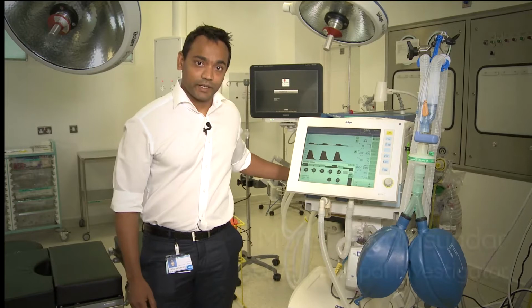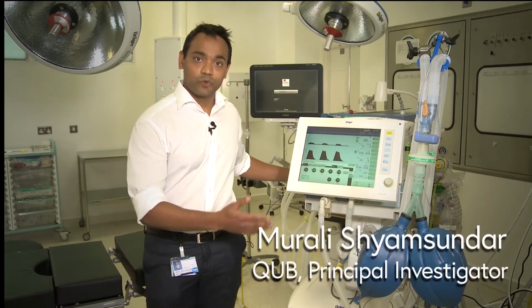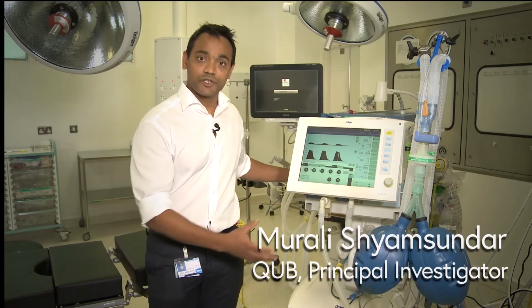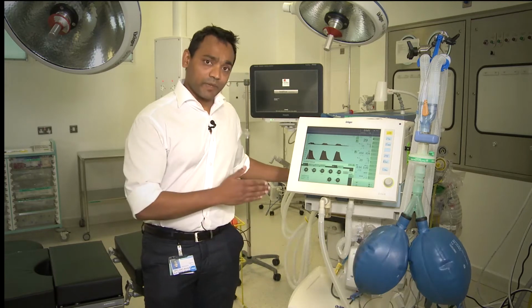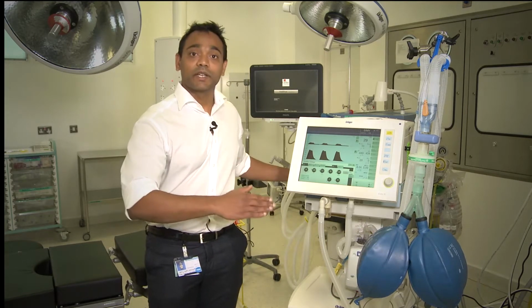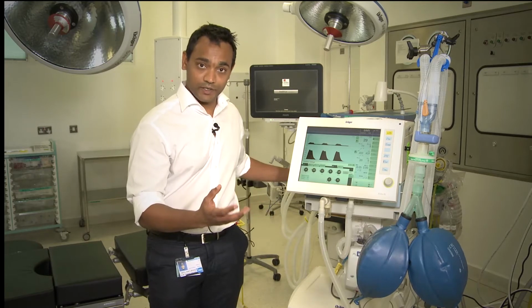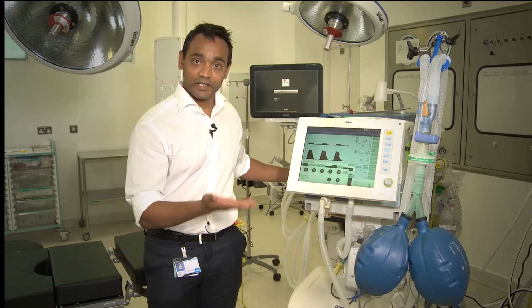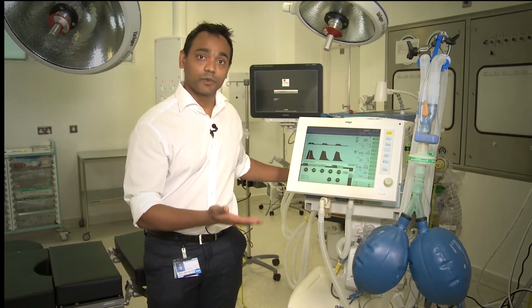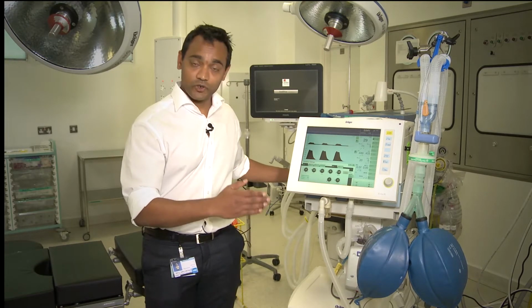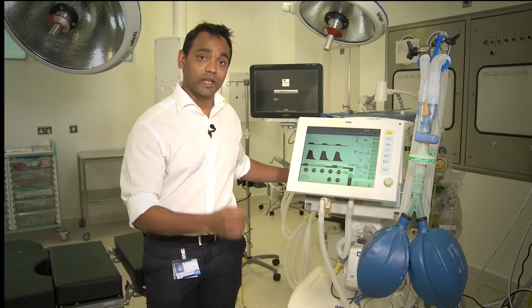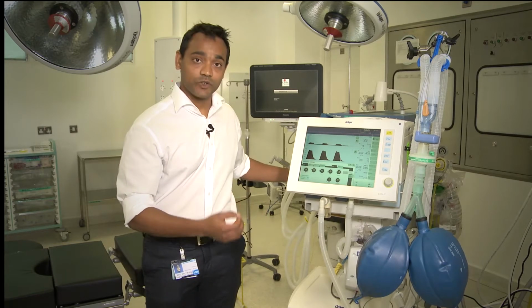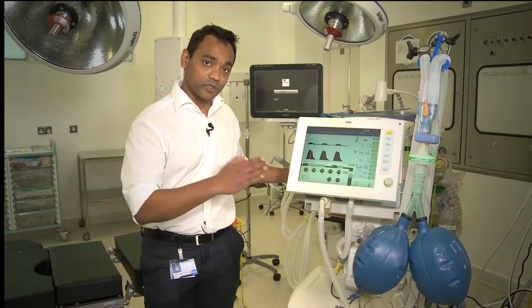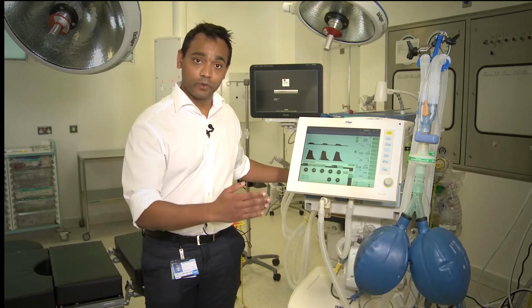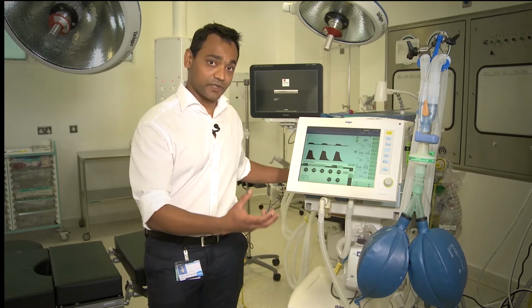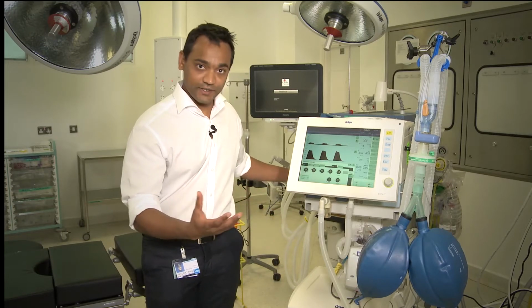This is a mechanical ventilator which saves lives by giving breathing support, and we have 2 bags which represent lungs. During mechanical ventilation, sometimes you can end up giving too much support, which translates to more gas flow or even increased pressures within the lung. And this itself, unfortunately, can damage the lungs and lead to increased risk of death and worse outcomes. Here I'll demonstrate 2 different amounts of gas flow, and you'll see how the bags which represent the lungs inflate to different sizes.